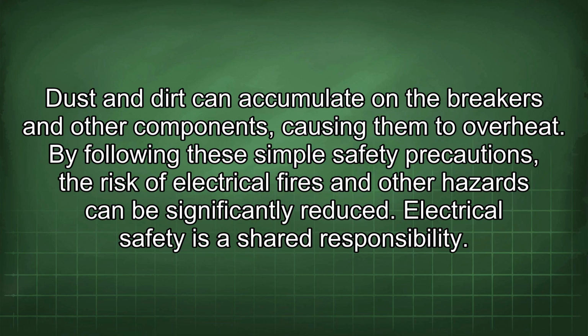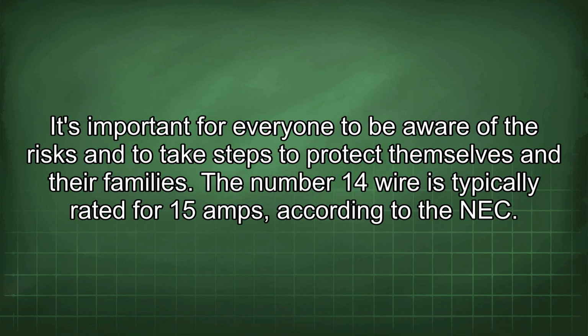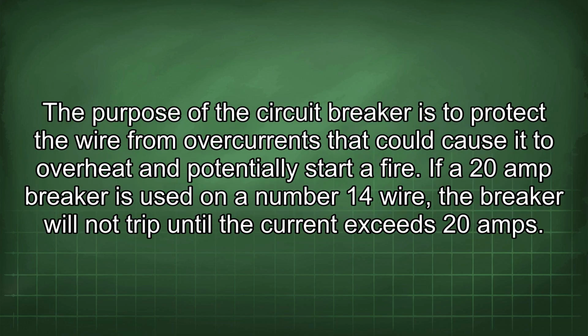Electrical safety is a shared responsibility. It's important for everyone to be aware of the risks and to take steps to protect themselves and their families. The number 14 wire is typically rated for 15 amps according to the NEC. The purpose of the circuit breaker is to protect the wire from overcurrents that could cause it to overheat and potentially start a fire. If a 20 amp breaker is used on a number 14 wire, the breaker will not trip until the current exceeds 20 amps.